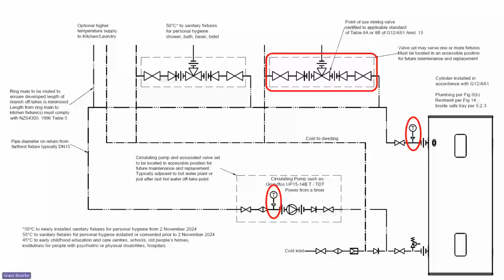If we then look at the offtake point mixing valve itself, there's a few things that we need to have in order to make this a good installation. It must be located in an accessible position, and I'm going to explain more about that on the next slide, why that is. So we can maintain it, we want an isolating valve, we want a non-return, and we want some swivels either side. And I'll talk on the next slide about why that's so important.